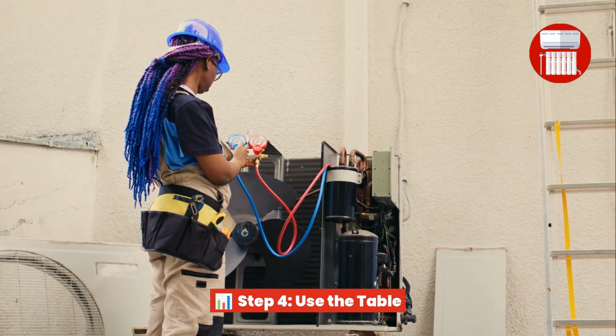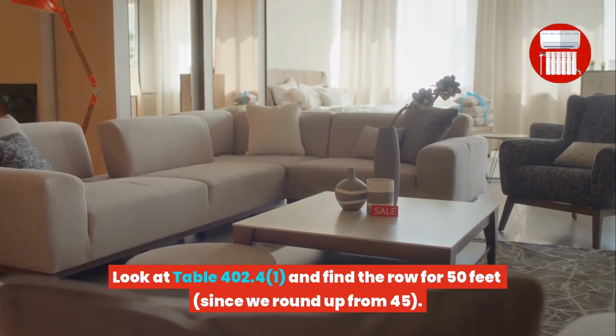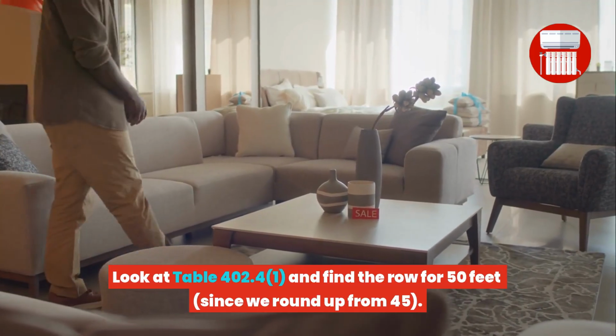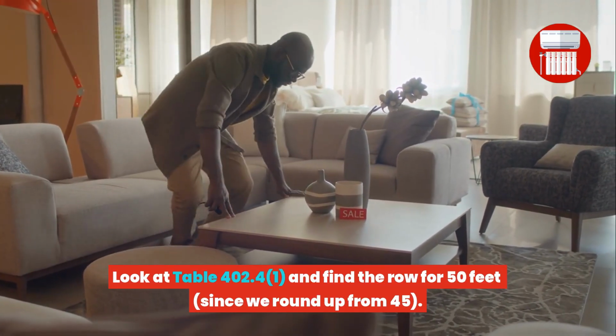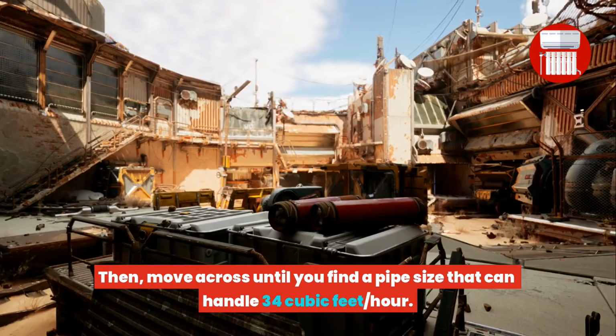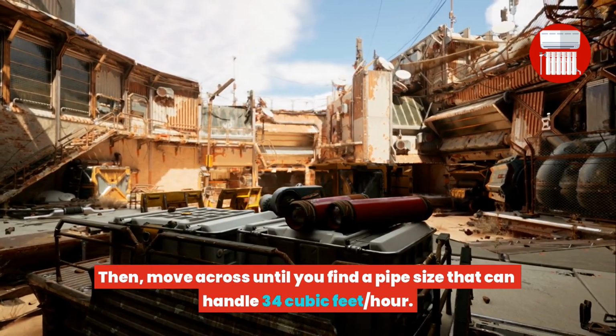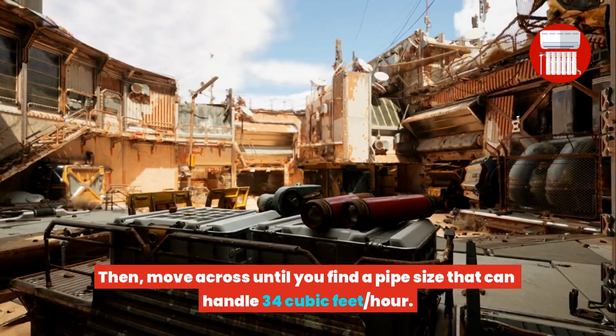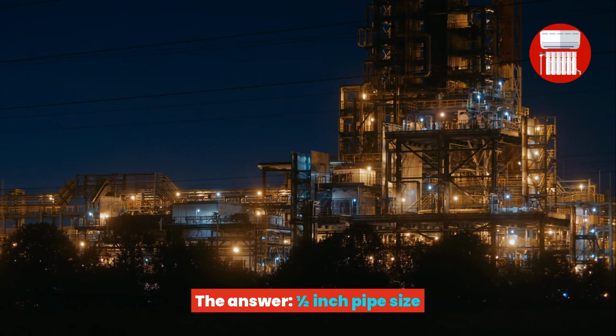Step 4: Use the table. Look at Table 402.4.1 and find the row for 50 feet, since we round up from 45. Then move across until you find a pipe size that can handle 34 cubic feet per hour. The answer: 1/2 inch pipe size.